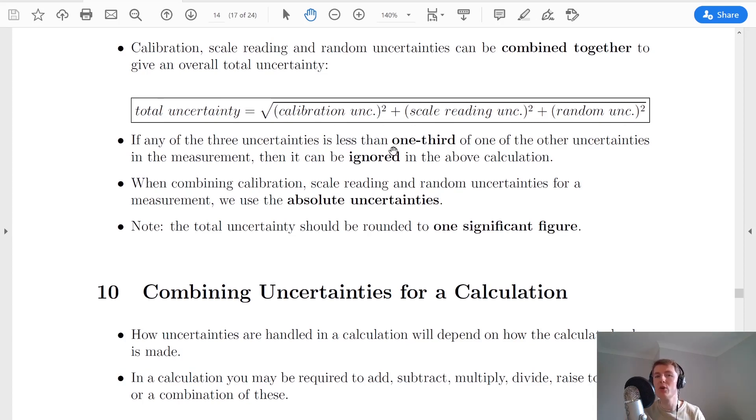There's one key rule that we need to be aware of when we're using this calculation. If any of the three uncertainties is less than one third of one of the other uncertainties in the measurement, or the biggest uncertainty, then it can be ignored in the above calculation.